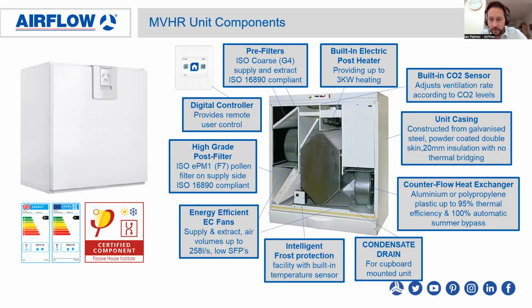You have a condensate drain underneath the heat recovery heat exchanger, because when the hot and cold air is crossing over, it does form some condensate, and this needs to be drained out of the unit. There's an intelligent frost protection on this unit with built-in temperature sensors. There's energy efficient EC fans. So there's 2 fans, a supply fan and an extract fan. These give very low SFPs to meet Part L.